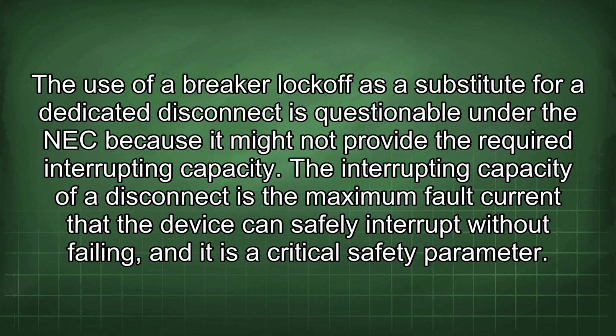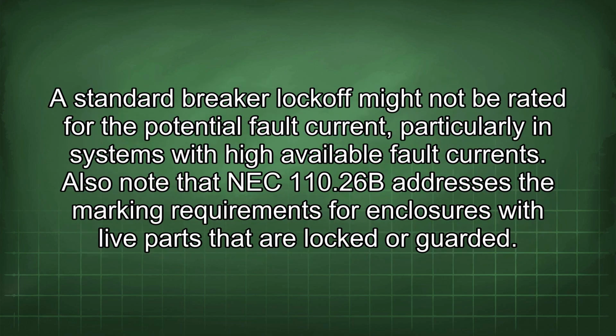The use of a breaker lockoff as a substitute for a dedicated disconnect is questionable under the NEC because it might not provide the required interrupting capacity. The interrupting capacity of a disconnect is the maximum fault current that the device can safely interrupt without failing, and it is a critical safety parameter. A standard breaker lockoff might not be rated for the potential fault current, particularly in systems with high available fault currents.